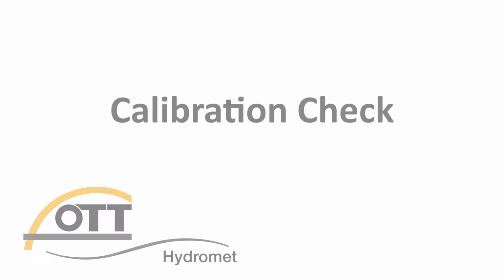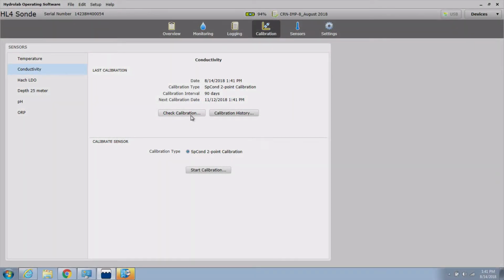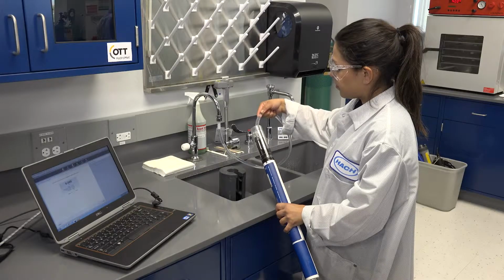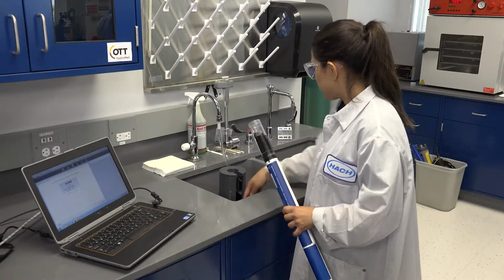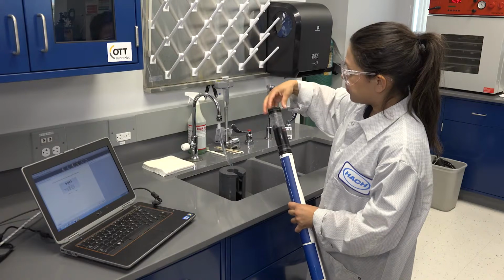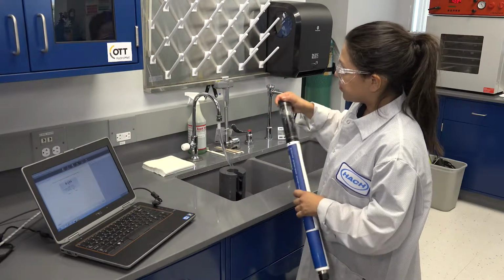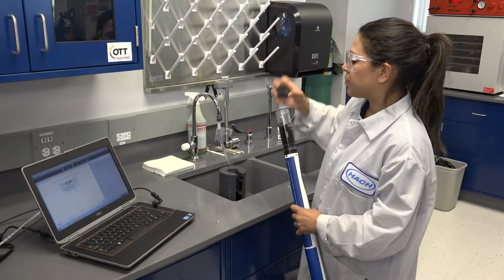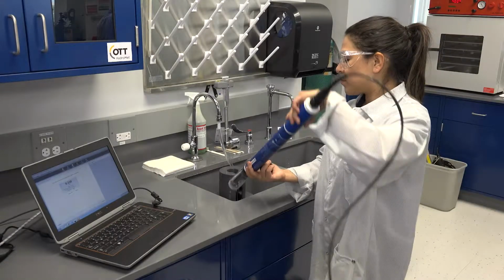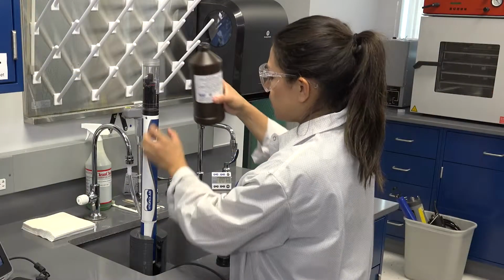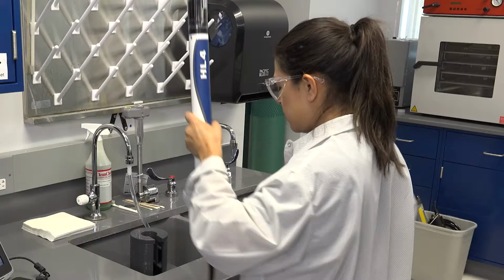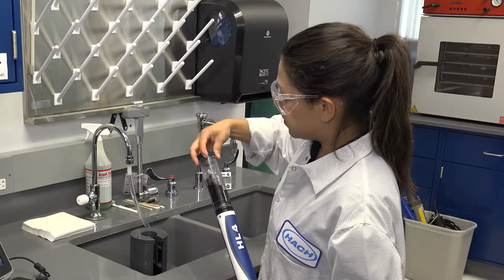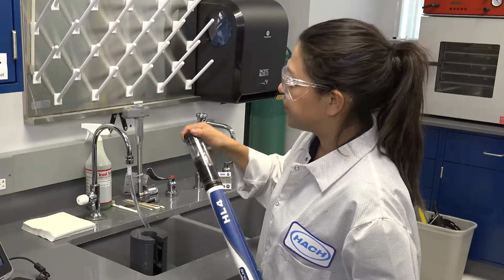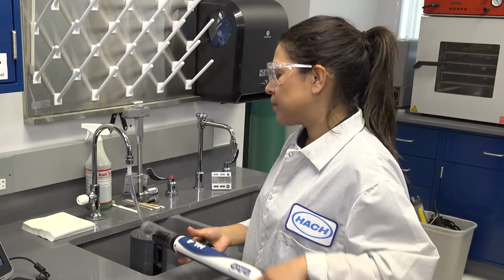Calibration check. After calibration, it is recommended to perform a calibration check to verify that the sensor slope is correct. You can access the calibration check in the Calibration tab of the Hydrolab operating software. Follow the instructions on the right side of the screen. To perform a calibration check, you will need a standard with a value that was not used in calibration. Be sure to follow the same steps of rinsing the sensor in deionized water as well as rinsing with the selected standard for optimal results.